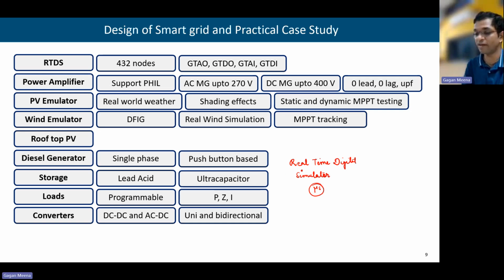We need not wait for several minutes as happens in the case of MATLAB, where for a large system, let's say a 432 node system, if we do a simulation at microseconds time step, then it will take several minutes. But this real-time digital simulator is able to do the same thing within microseconds itself. It's very quick. That's why it is called real-time. It is emulating as if it's a real system. And that's why if we do a hardware simulation using RTDS, it is similar to operating in real time.